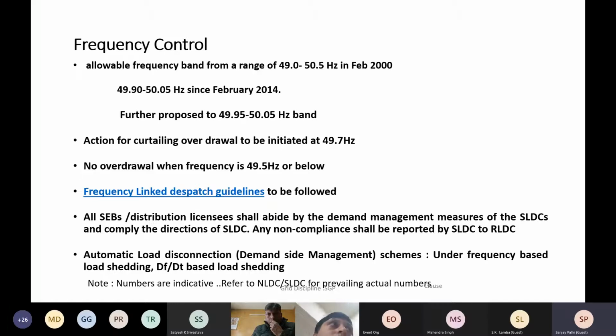Now this enables actions to be taken at various levels, at generation level, transmission level, and distribution level, to maintain the frequency in a very narrow band. It has become possible, and various actions and technological developments have permitted the grid to be operated in a narrow band, and that's how the grid also becomes very reliable and stable. We are all aware of the frequency linked dispatch guidelines, and we started with the ABT regime, where there were frequency linked commercial mechanisms for the scheduled and unscheduled interchanges over transmission lines.